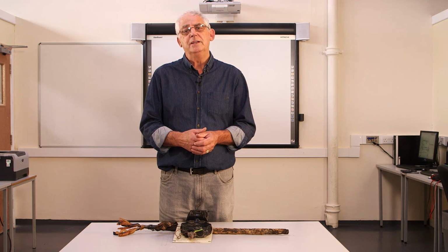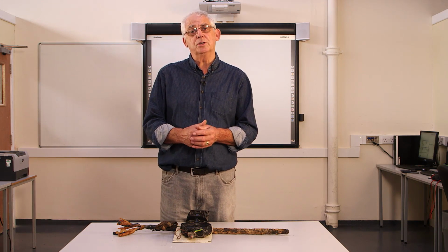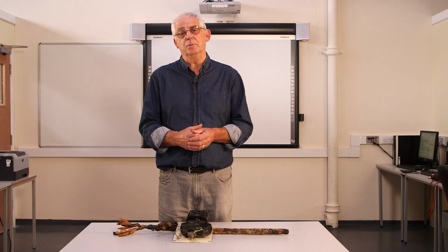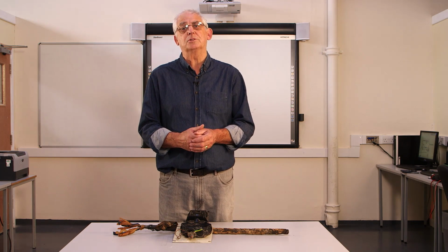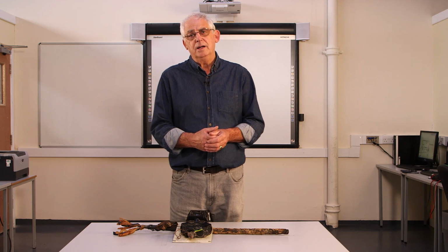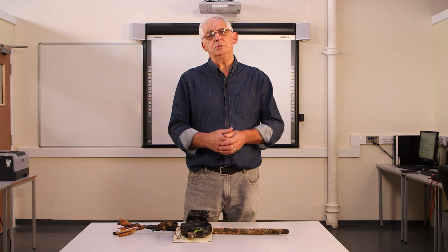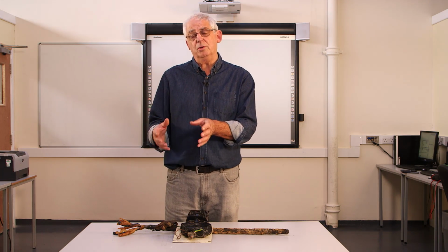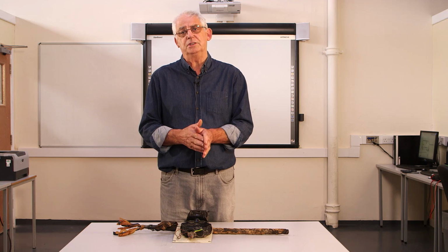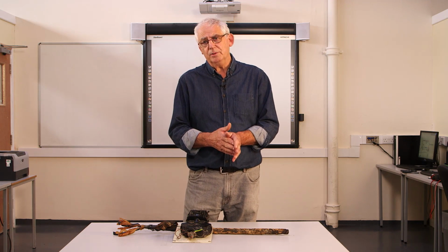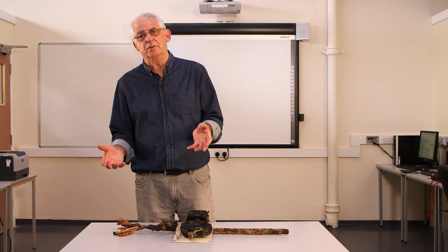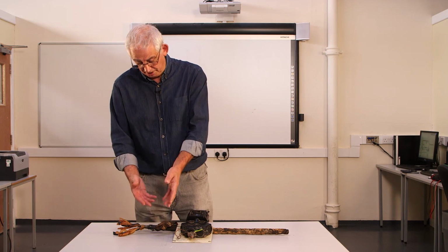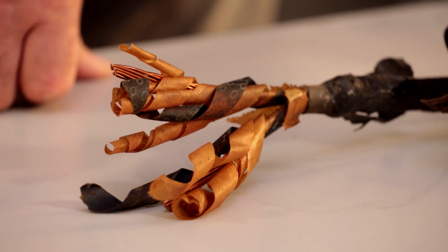If we first look at a TNS system, just need to look really at the type of cable. TNS system, the earth return path back to the transformer would be through the sheath of the supply cable. Not a system that's installed now, although it is still a very, very common system in this country. And the way it works is the cable's buried underground. It's going to be an older type of cable, same as you can see here.